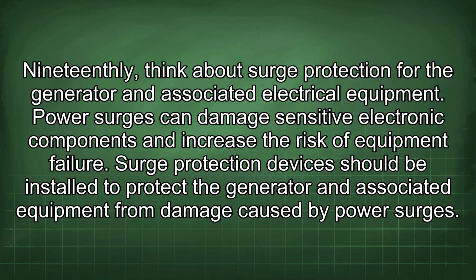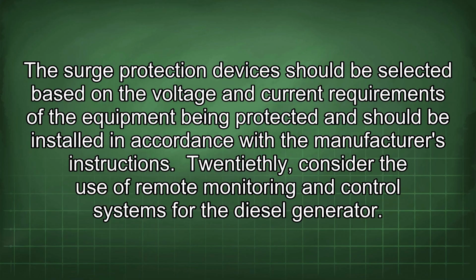19thly, think about surge protection for the generator and associated electrical equipment. Power surges can damage sensitive electronic components and increase the risk of equipment failure. Surge protection devices should be installed to protect the generator and associated equipment from damage caused by power surges. The surge protection devices should be selected based on the voltage and current requirements of the equipment being protected and should be installed in accordance with the manufacturer's instructions.